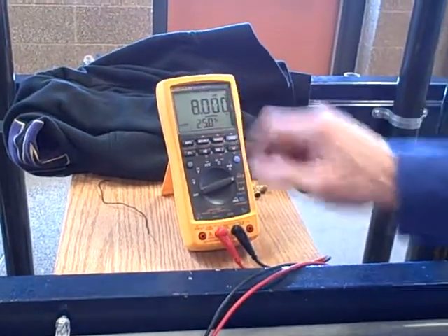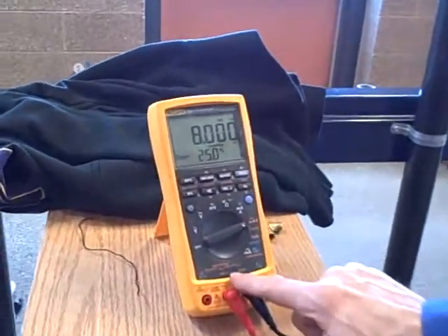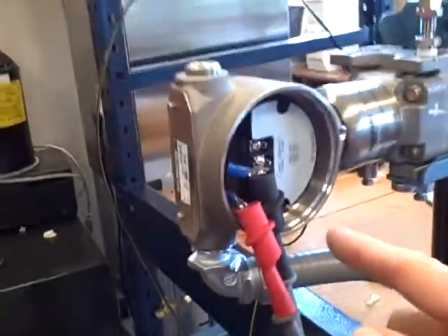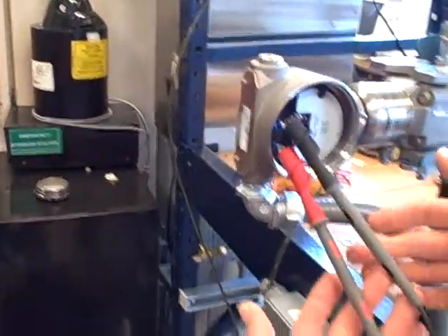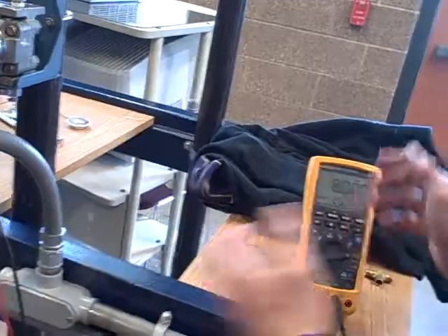We're using the Fluke Model 789 process meter to simulate a transmitter. Notice our connection to the transmitter. The connection here, we have replaced the connections to the transmitter with the test leads to our process meter. What this means in the simulate mode is the process meter is now acting as a current regulator.